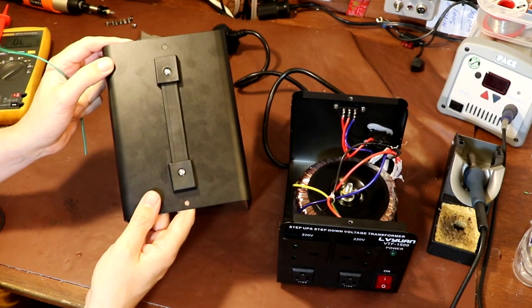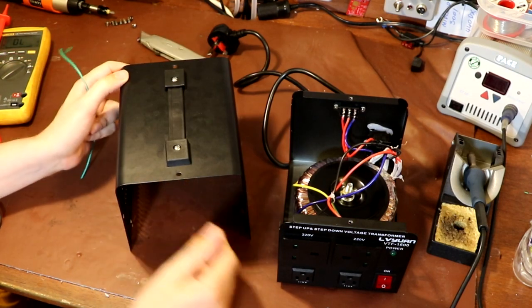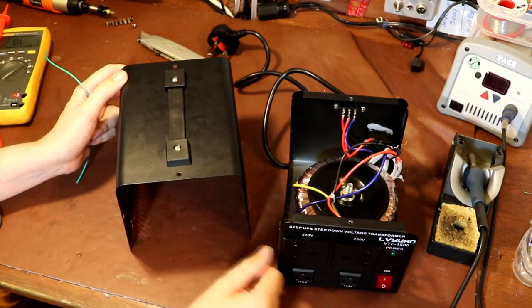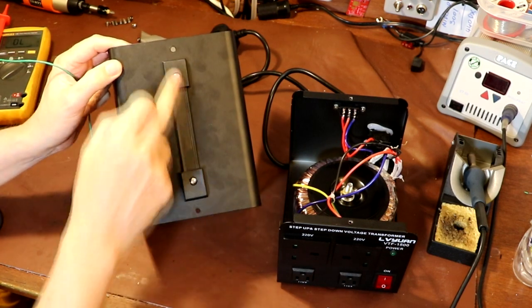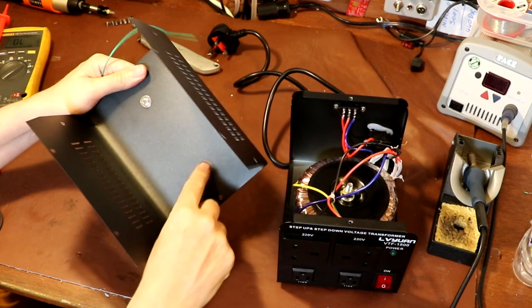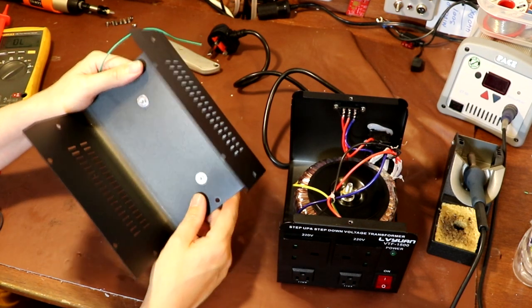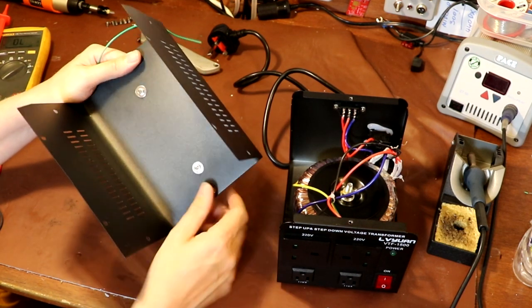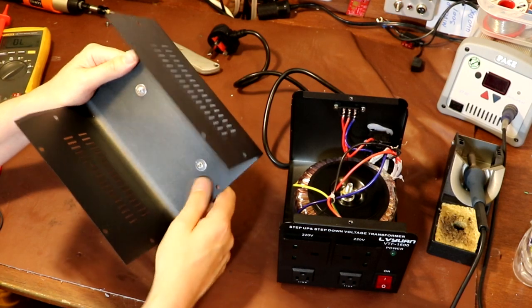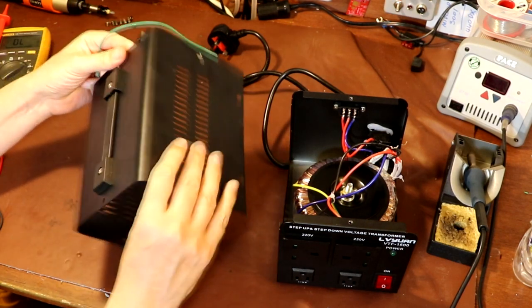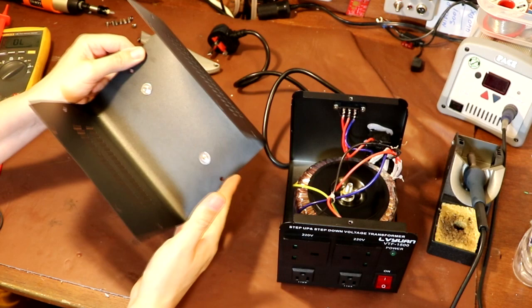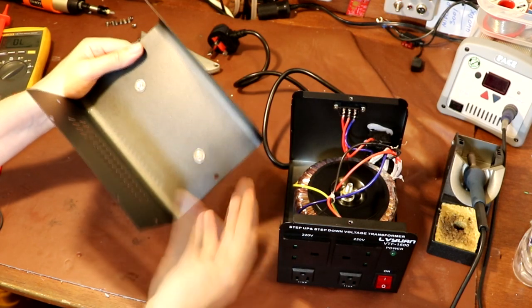Earlier I performed that electrical safety test, but I actually did it on one of the screws on the side of the casing. It probably would have been more sensible to have done it off these fixings here, because that would have actually proven if this case was properly earthed. I suspect if I had tested these fixings, we would have gotten a fail, because there's a lot of paint on all this. But of course I didn't know how this was assembled before I did the testing.